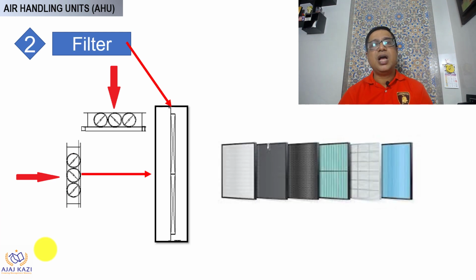The next item is, after the damper, the air passes through the filter, and this is how the filter comes in. There are various types of filters depending upon the filtration level required inside, whether it is a pre-filter, micro V filter, MERV filter, or HEPA filter. It will depend on what kind of filtration level you require inside the area to be conditioned.